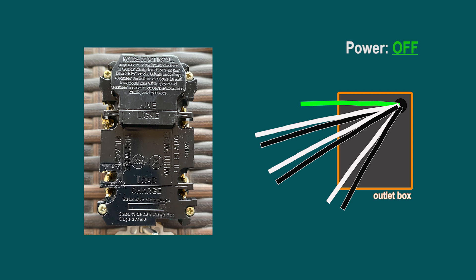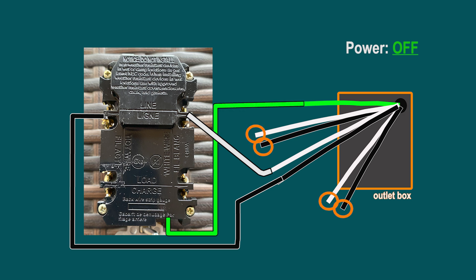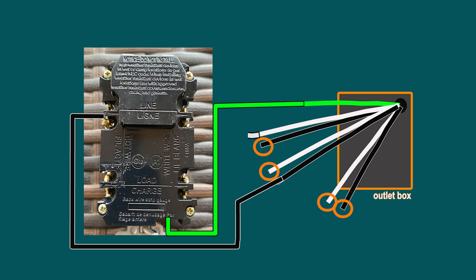To verify the connection, wire up the hot to the brass screw on the line and the neutral to the silver screw. Ground is connected to ground. The rest of the wires at this point are not connected and not touching each other. Plug in a light into the outlet and turn on the breaker. If the light is working, you connected the proper hot and neutral. If it does not, shut off the breaker and try another neutral wire from your selection of non-powered ones. Just make sure that only three wires remain connected to the outlet at a time and the rest are not. Eventually, you will find the proper neutral and the light will come on.